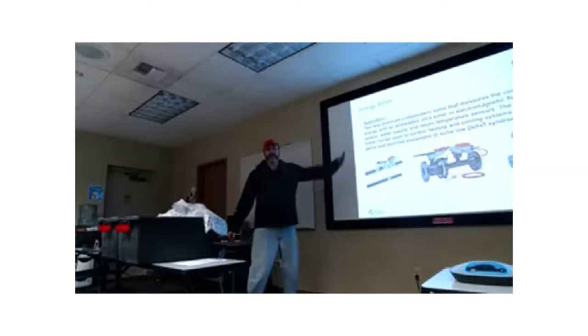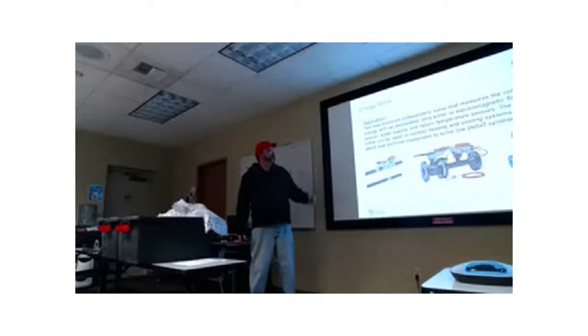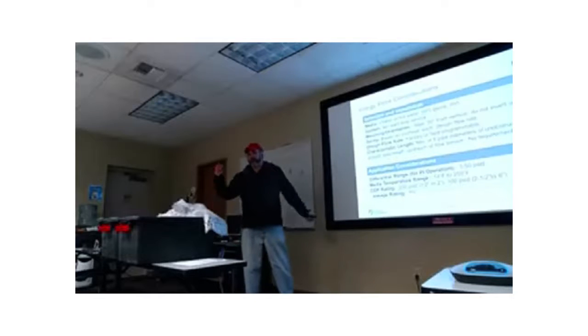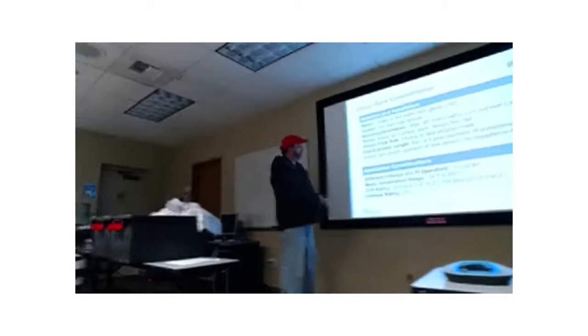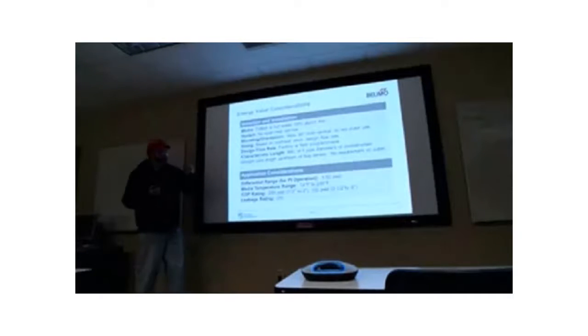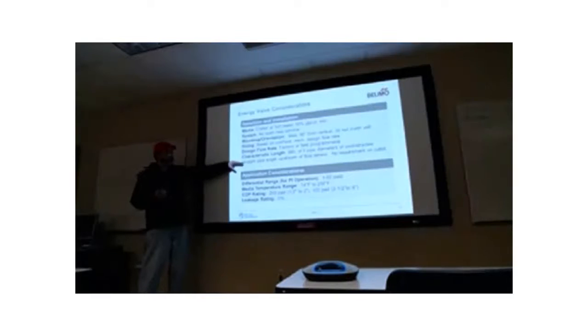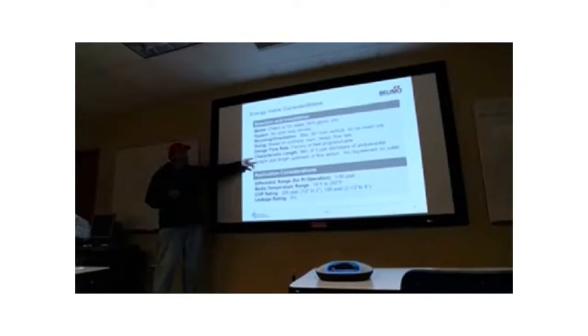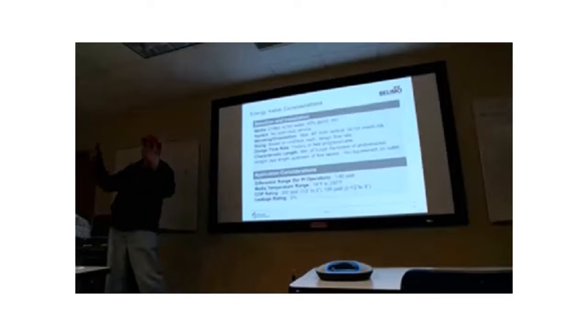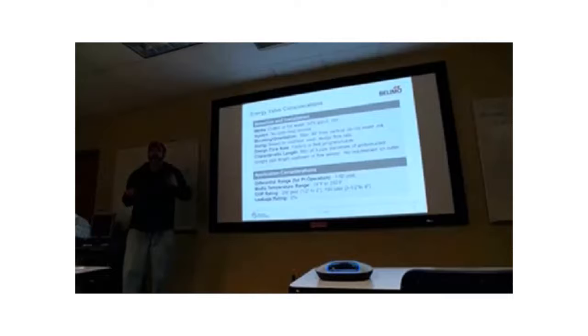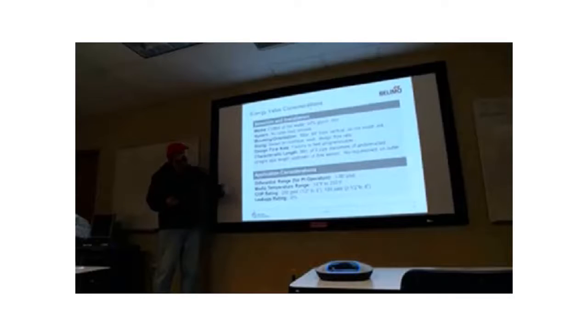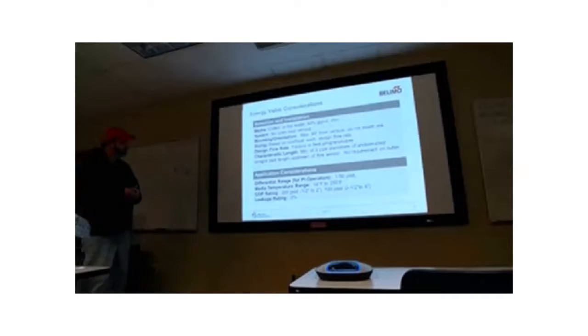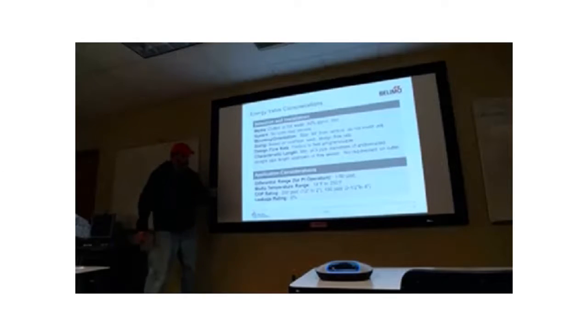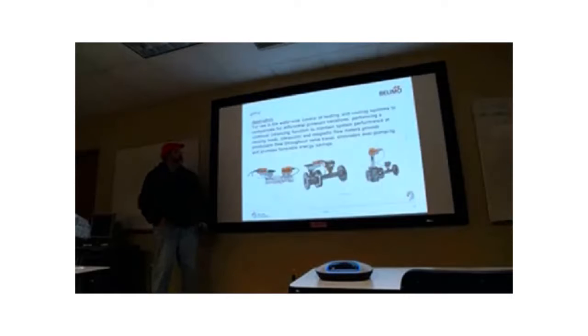All right, so that's the energy valve. That's sort of our flagship valve product. One thing though, and you guys don't have to deal with this, but installation would. Because it's a flow meter, you have to have 5 pipe diameters of straight pipe upstream of that meter, right? Because the flow profile has to be right. So that causes some problems as far as retrofitting and things like that. But it works out pretty well if you account for it in the pipe.